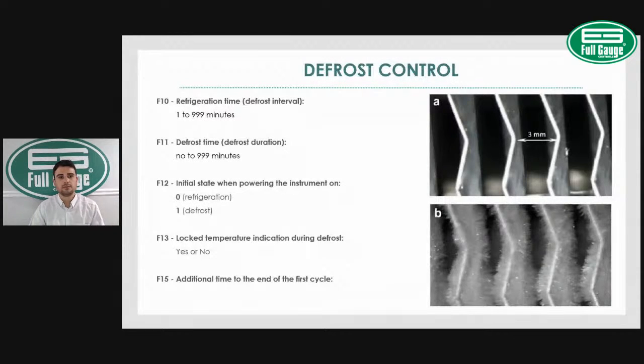Those are the defrost functions available with the 512. However, the 2 most common ones, the ones that really need to be changed, are F10 and F11. Those are the most critical defrost functions. The other 3 functions will actually provide you a better performance. They will improve the performance of your refrigeration system and will definitely save electricity.